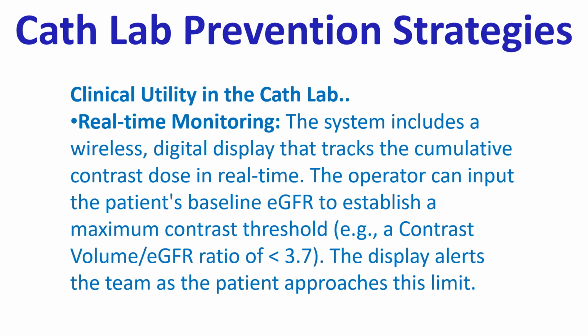Real-time monitoring. The system includes a wireless digital display that tracks the cumulative contrast dose in real time. The operator can input the patient's baseline eGFR to establish a maximum contrast threshold, for example, contrast volume to eGFR ratio of less than 3.7. The display alerts the team as the patient approaches this limit.